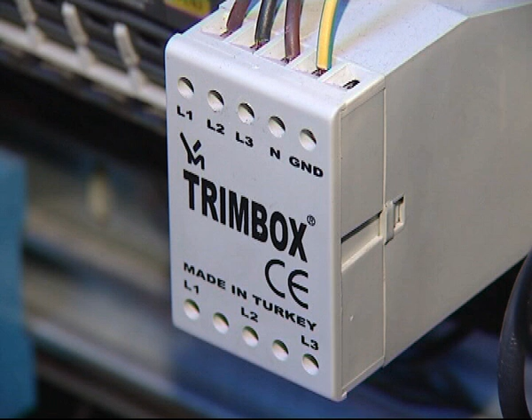The Trimbox overvoltage protector is connected with 2.5mm cross-section, highly conductive cable, with earth and neutral connections, to elevator inverter feeding fuse outlets in the intermediate distribution panels.